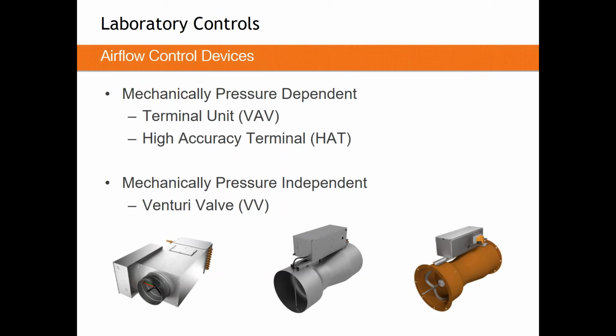What we like to do is take these three styles of devices and group them into two different groups: those that are mechanically pressure dependent and those that are mechanically pressure independent. So in the first group, the dependent type, are VAV boxes and high accuracy terminals. These two types of devices are really substantially similar, if not frankly identical. And with a type of device like this, and we'll dig more into them, they measure airflow. Pressure and airflow are going to be intimately tied together. They're essentially the same value. So mechanically speaking, these devices are pressure dependent.